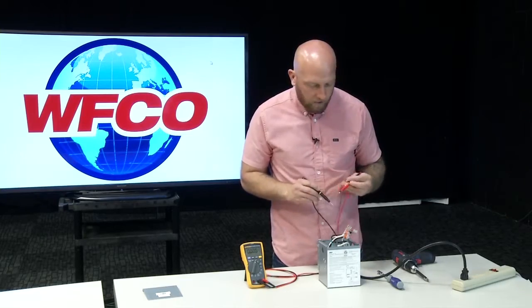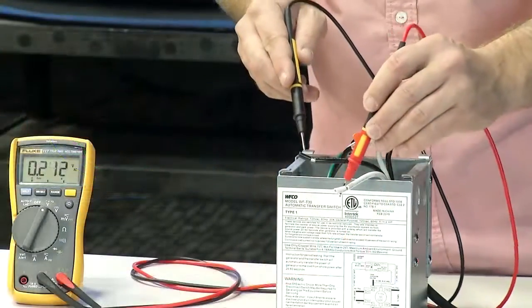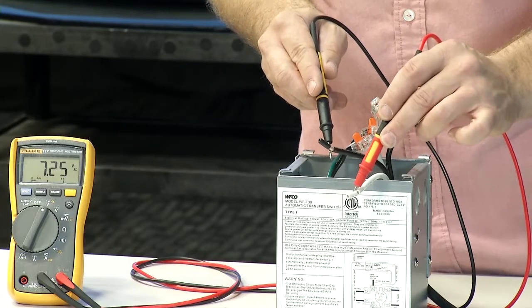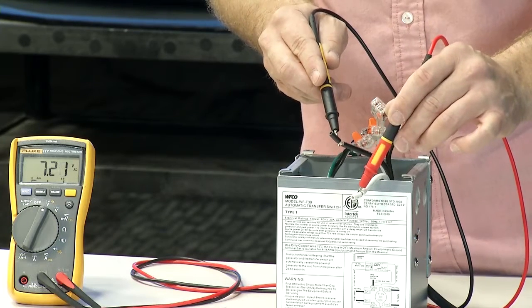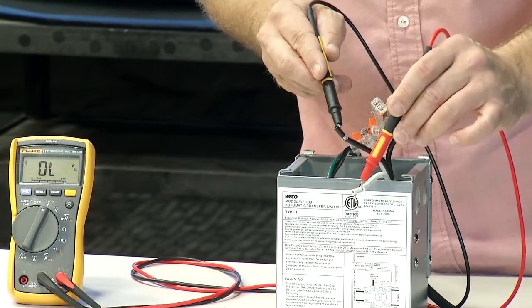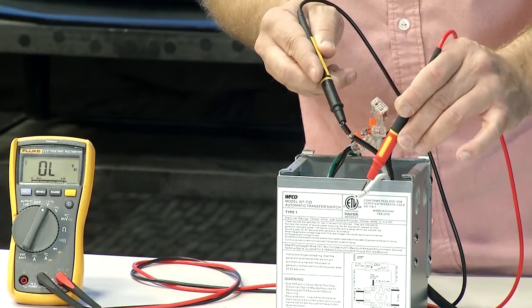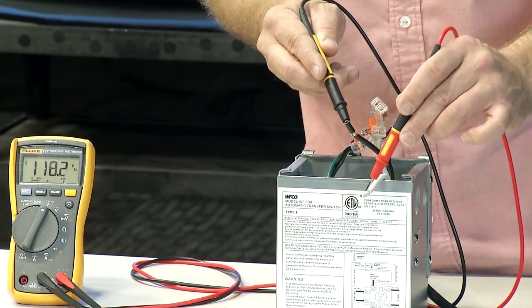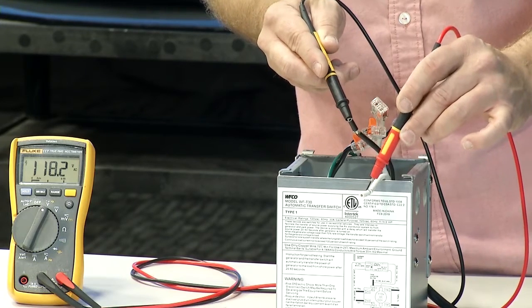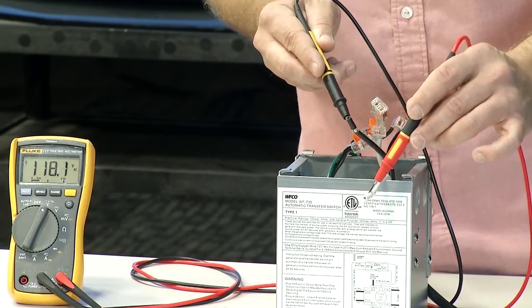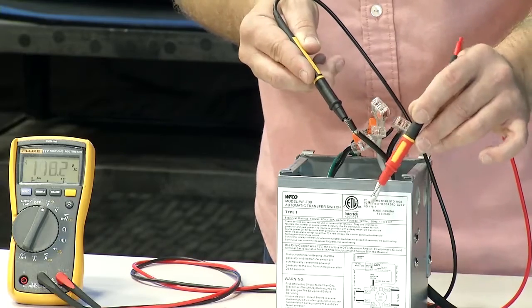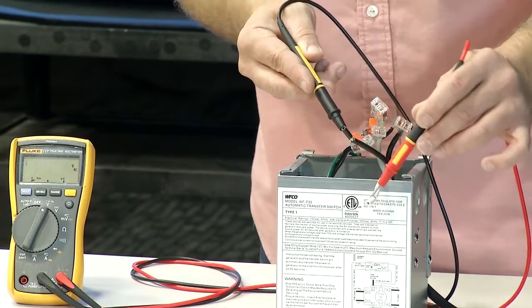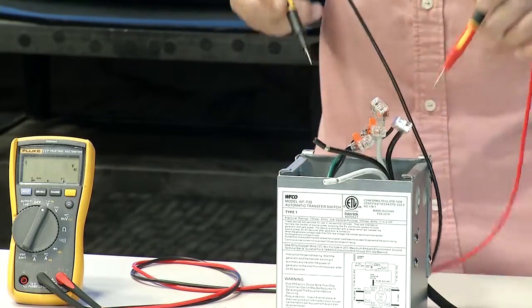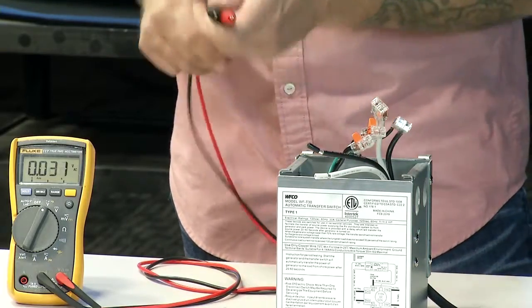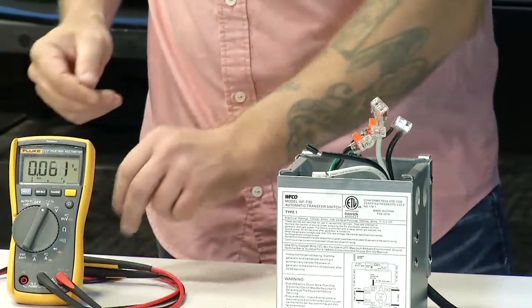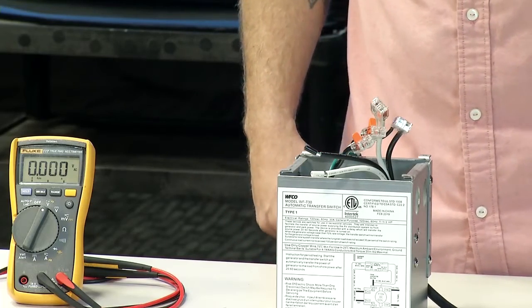We just heard an audible click. Now you're gonna go back to your panel wires. Once you get your meter on there right, you've got your 118 volts coming out from your generator. That 30-second time delay is the whole purpose of a transfer switch—it gives the generator 30 seconds to do its self-diagnostic, so it's not putting out high or low voltage and damaging your AC appliances in the coach itself.